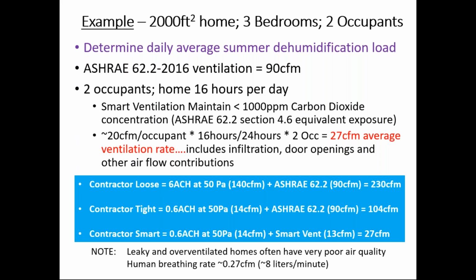Now, I also want to mention something somewhat ironic and maybe not so common sense: a leaky and overventilated home, we find from our field studies, typically has very poor air quality. That's because where it leaks or where it's overventilated isn't necessarily occupied. So a home that's simply dumping 90 CFM of air into the house, spreading it into every room, but 80% of the house isn't occupied, means 80% of that fresh air didn't do anyone any good. You need other systems, distribution systems, to actively figure out how to move that to where it's going to be beneficial.